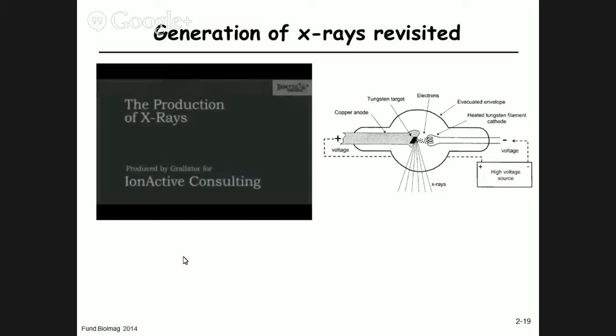To recap x-ray generation: we have the positively charged tungsten target on one side, the negatively charged filament cathode on the other, and a high voltage source providing the voltage difference. We heat the cathode filament, electrons are liberated, they are accelerated toward the target, and when they hit the target they produce x-rays.